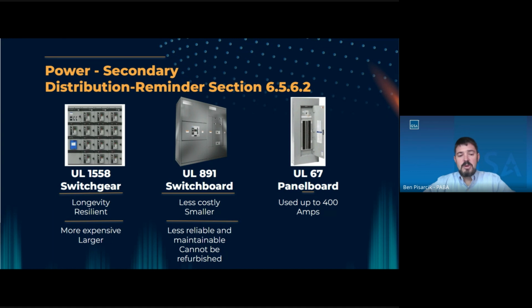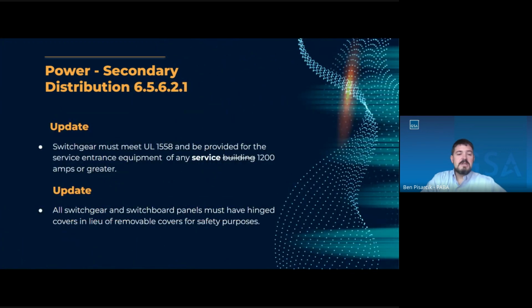And then your typical panelboard, UL 67, we typically use those up to 400 amps. More commonly, 225 amps are very typical throughout our buildings, and I just wanted to include that there for reference. So what did we change in this section? Same section, the switchgear must meet UL 1558 and be provided for the service entrance equipment of any service. We had previously said building of 1200 amps or greater, so 1200 amps is the key number there. But we had different scenarios where folks said, well, it's not a building, so I don't have to do it. So we changed it to a service. So the main service to any facility or whatever it may be must be draw-out switchgear if it's 1200 amps or greater.